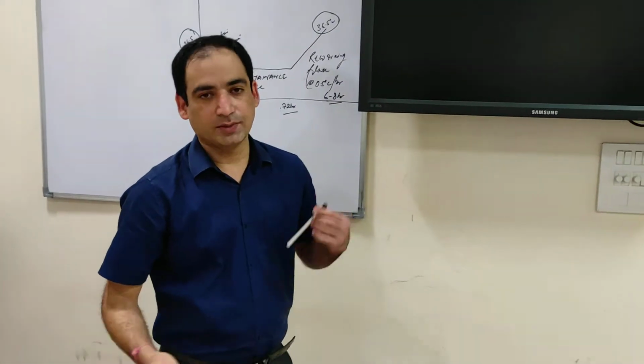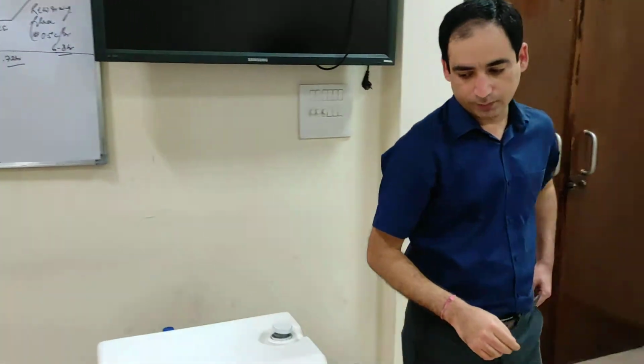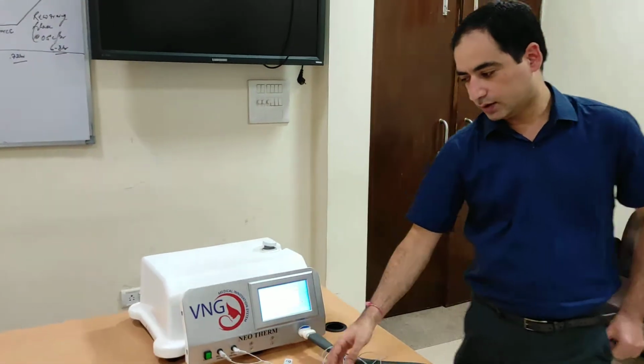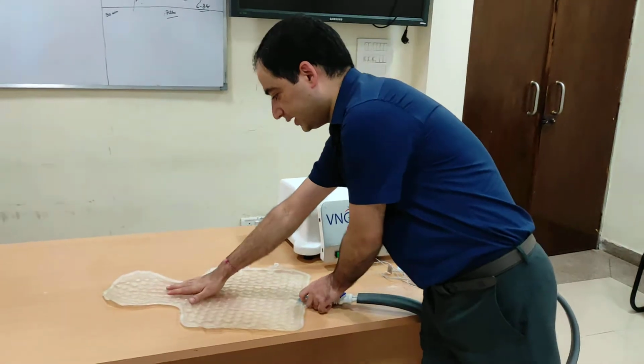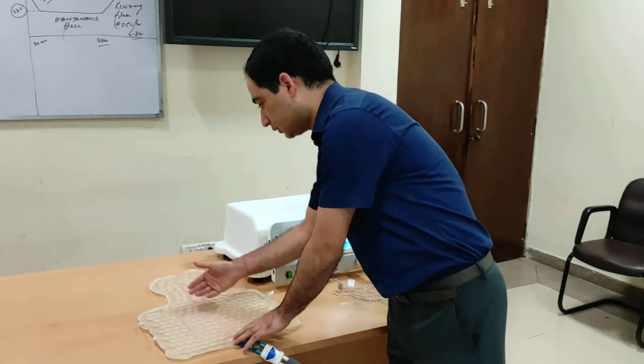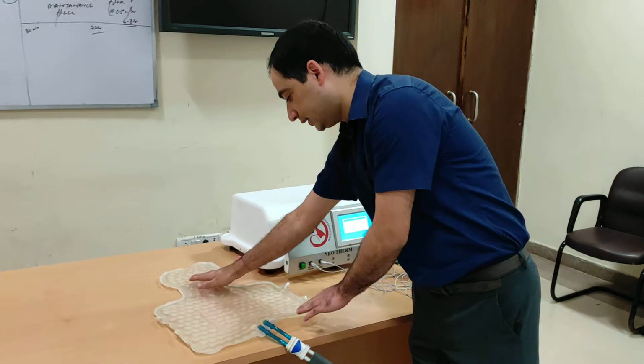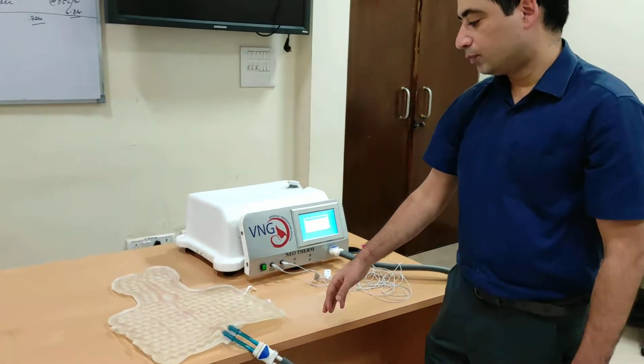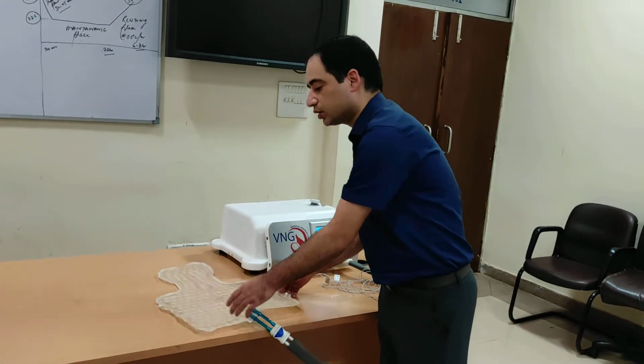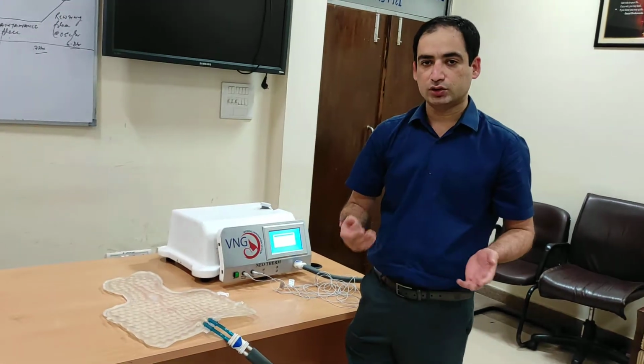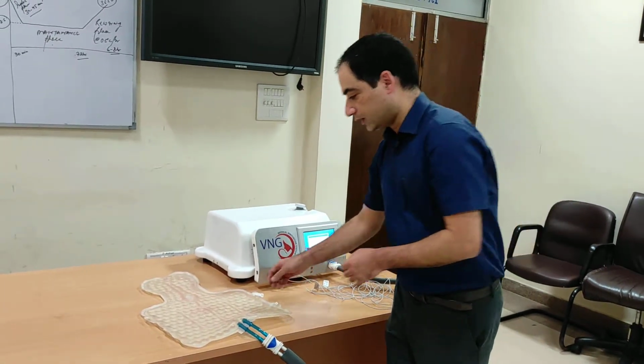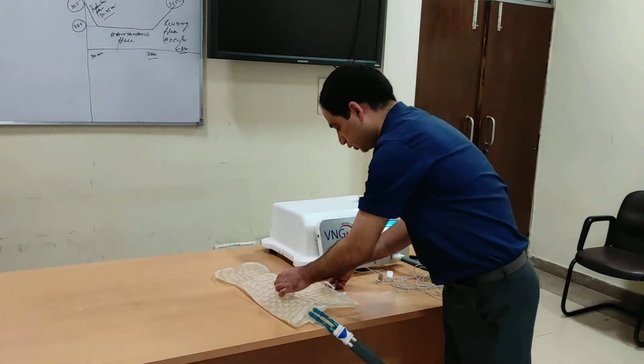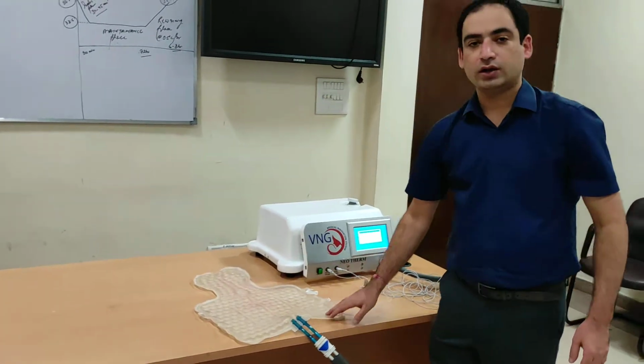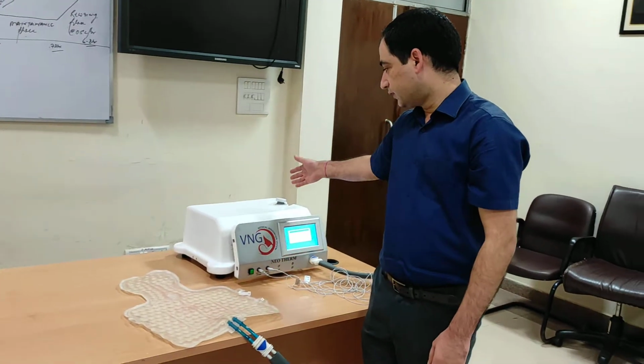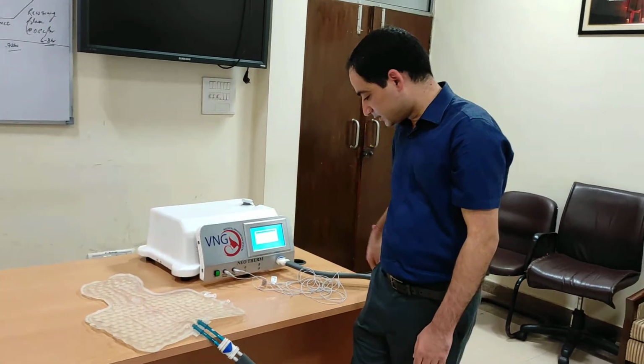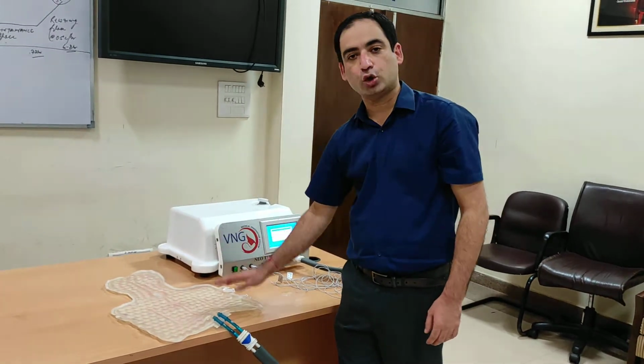Then how to place the baby in therapeutic hypothermia. As told previously, this is the baby jacket. This is the head end and this is the body end. The baby has to be placed, the head on the head end, and this is for the rest of the body. Before closing this jacket, ensure that you have placed the umbilical lines, ideally both umbilical vein and umbilical artery, and once they are placed, you should close the jacket. Remember that you do not need to fill this jacket. Whatever coolant you have filled inside the machine will automatically circulate inside this jacket, so it will get automatically refilled.